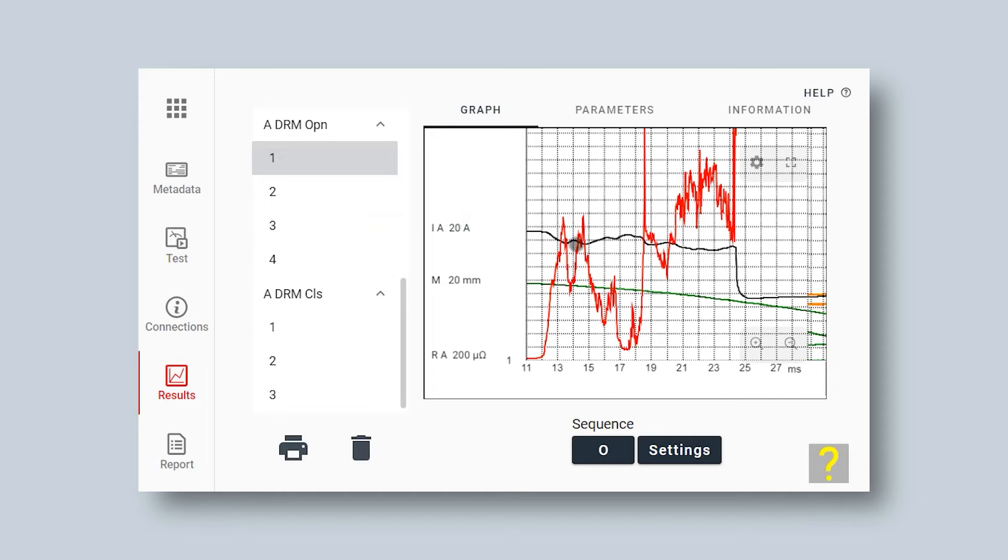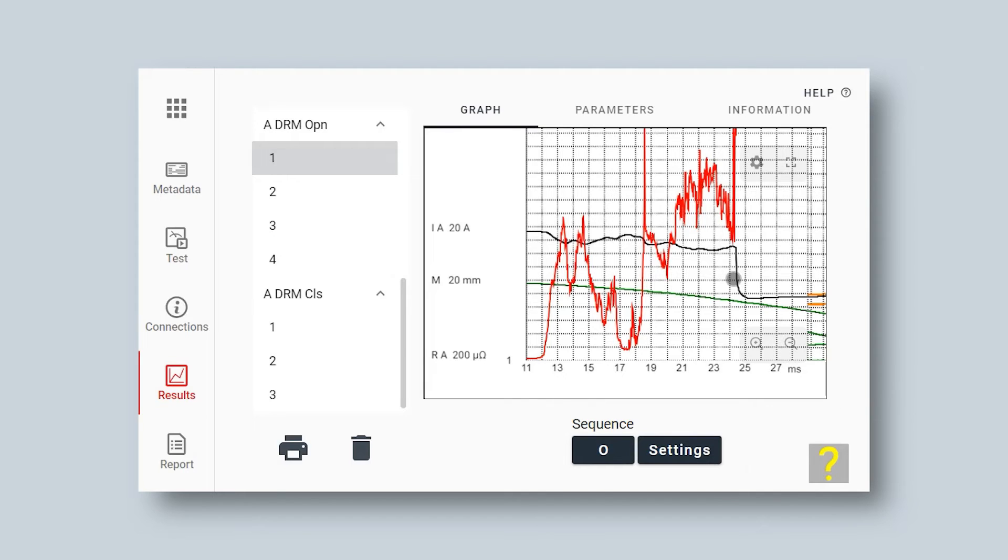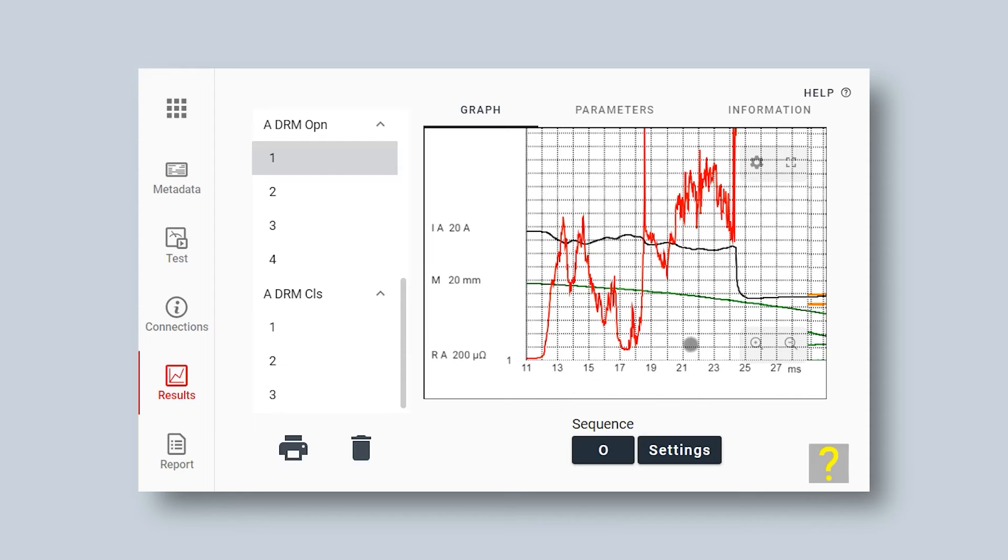I start looking for my DRM points. First point, I see my current in black. And here the arcing contact opens and the current drops. The current drops at 24.5 milliseconds and that is my final contact point of opening. The current doesn't go to zero because I have my object grounded on both sides.